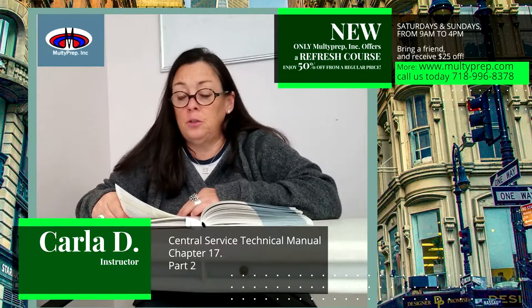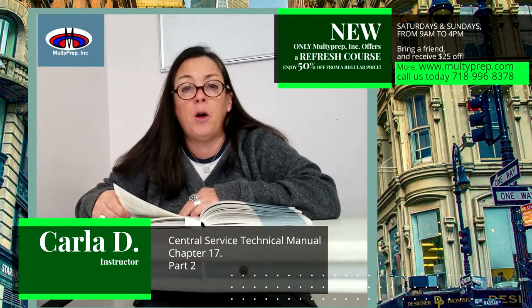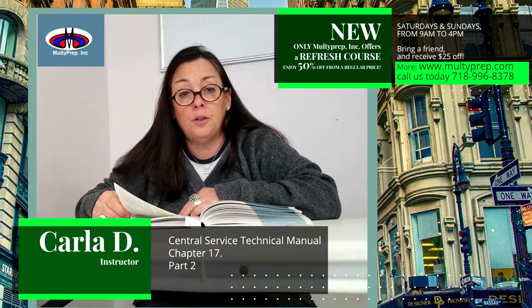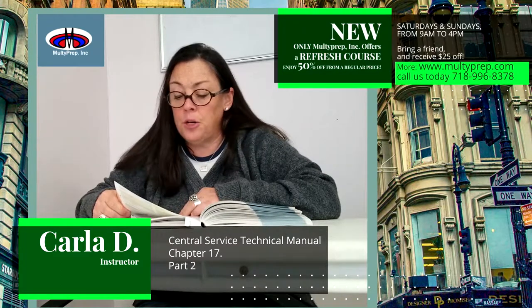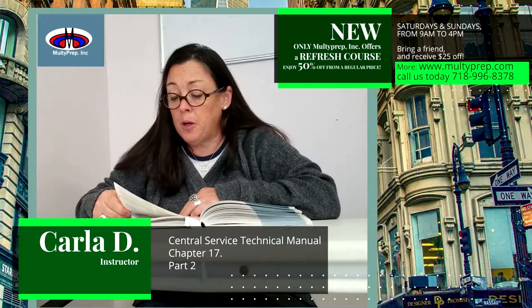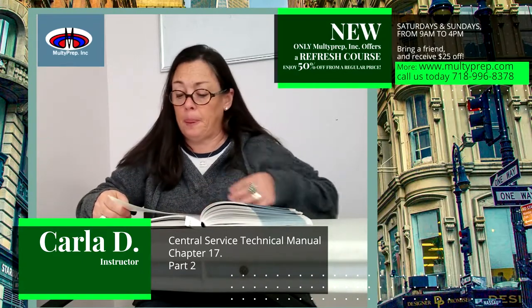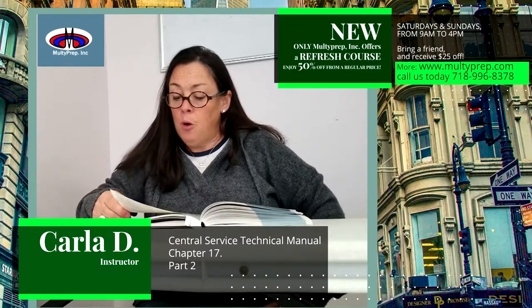10.9. Definitions. Validation: procedures used by equipment manufacturers to obtain, record, and interpret test results required to establish that a process consistently produces a sterile product. Verification: procedures used by healthcare facilities to confirm that the validation undertaken by the equipment manufacturer is applicable to the specific setting. Important note: while product verification can be accomplished in a healthcare facility, the parameters validated by the manufacturer cannot be changed and properly verified.